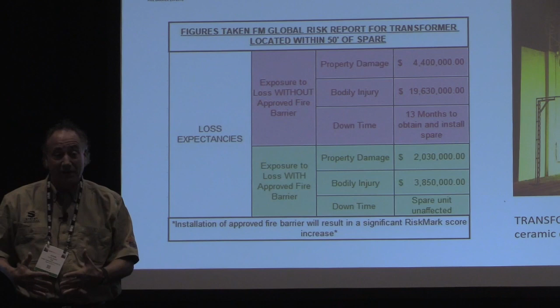For your catastrophe insurance, for your business and continuity insurance, and even pollution insurance will show you. But you can see this transformer, which is a typical old transformer, on fire, 6 to 8 hours, throwing ball bearings and shards. If we could protect you from that failure, protect your business, your hospital, your facility, your schoolyard, you're going to achieve lower insurance rates. There's something called a RiskMark score. Transformer fire barriers raise your RiskMark score, thereby lowering the impact, lowering your insurance rates.